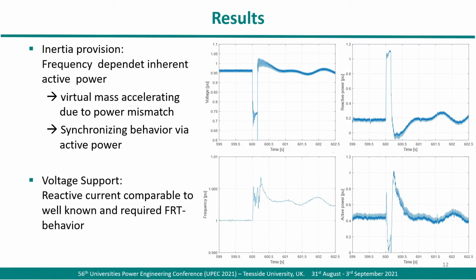This behavior can be explained with the power mismatch between nearly constant infeed on the DC side and the reduced outgoing power. The virtual rotating mass would be accelerated. Since the virtual mass is configured to be low compared to the synchronous generator, it will accelerate faster than the other synchronous generator. Therefore, it has to decelerate for synchronizing.